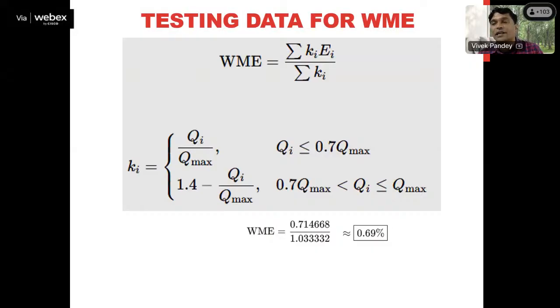So suppose you have selected that you are going to perform the test at a flow rate of, say, 0.4 liter per hour. And that 0.4 liter per hour is less than 0.7 times Q maximum. This flow rate which we have decided is less than 0.7 times the maximum flow rate. So obviously the K value will be calculated using Qi upon Qmax. The formula used will be Qi upon Qmax; Ki will be Qi upon Qmax.